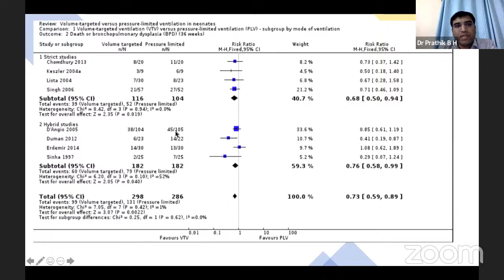This is the same forest plot of what I told just now. There is a reduction in death or BPD by almost 27 percent. So one of the important drawbacks of volume guarantee ventilation, not a drawback, it is a need: there should be a proper flow sensor at the patient end. If the flow sensor is not functioning, or if there is a malfunction of the flow sensor, then the ventilator will switch back to the PIP limit, whatever you are giving.